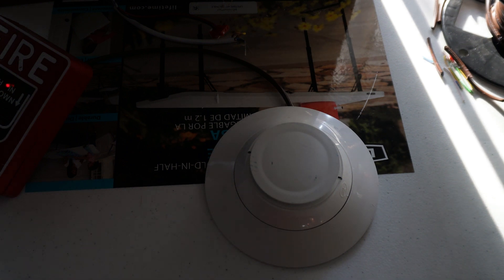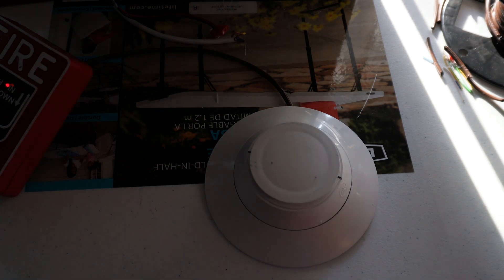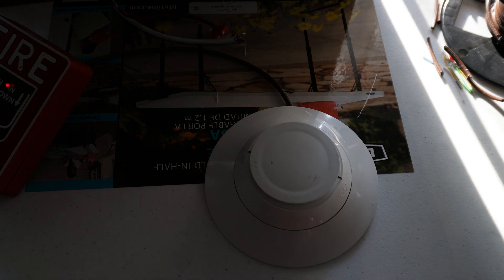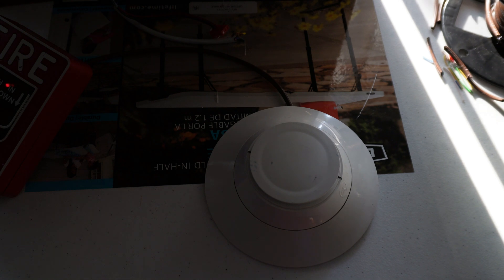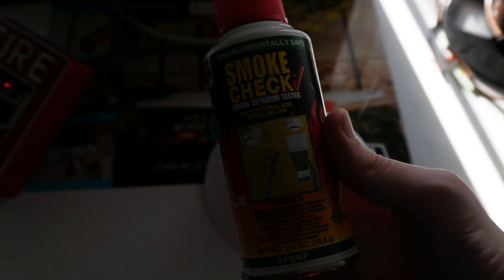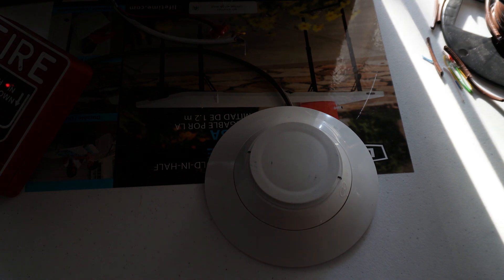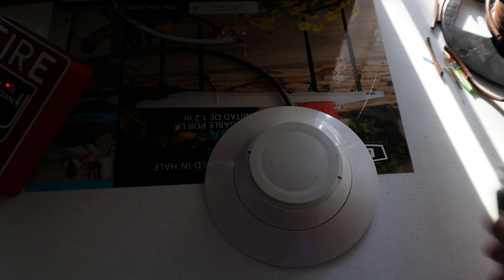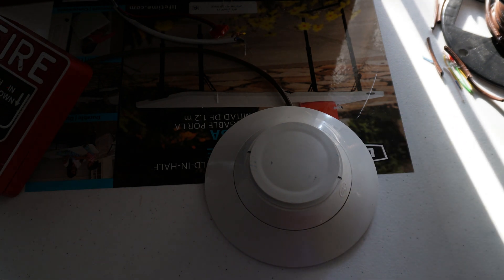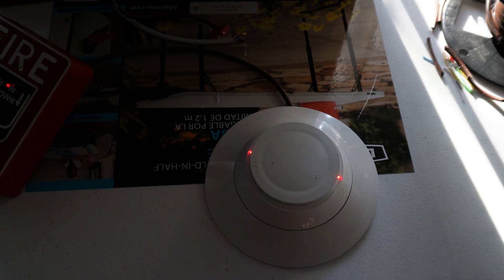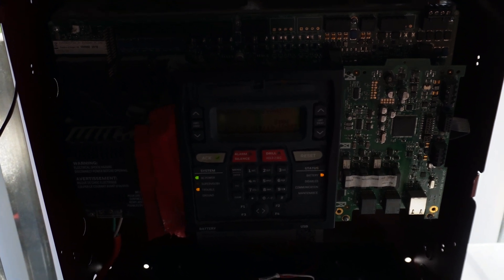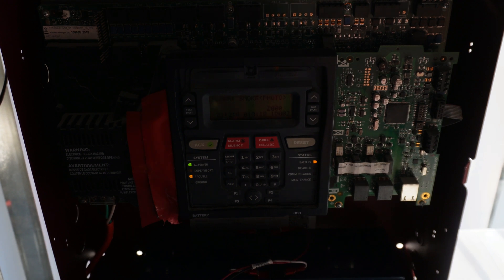Now the moment of truth, an operational test. This detector doesn't even have a button to push to test it or anything. So we're going to test it the more fun way, using smoke check. I'm just going to give it a whiff of this. Let's make it trigger. Oh yep, there we go. The lights are solid, meaning that it triggered. And the panel is now in alarm. The smoke detector is functioning as it should.